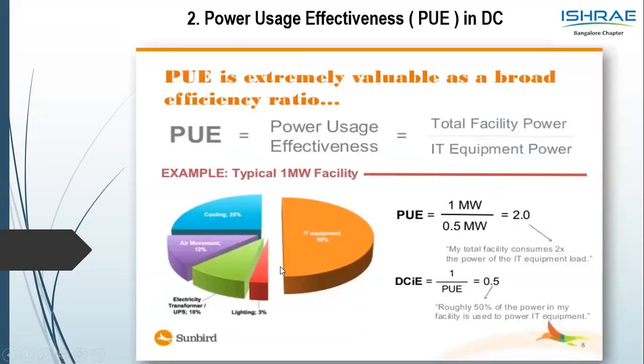So the next important point, apart from the tiers, tier 1, tier 2, tier 3, tier 4, where we looked at the redundancy in power and cooling. As we get into the next slide, PUE, we keep hearing of PUE in a data center, power usage effectiveness. What is PUE? PUE is the total facility power divided by the IT equipment power. So what is facility power? Facility power is the power consumed in the facility, that is in terms of cooling, air movement, UPS or lighting, divided by the IT power. What is the IT power? The power drawn by the servers and the PDUs. So, giving you a quick math, the PUEs would be averaging from 3 to 2.51.